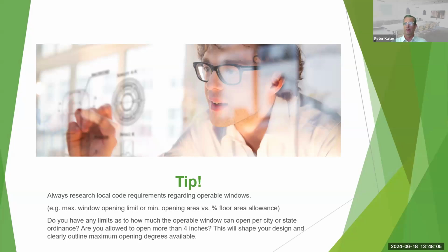In many commercial buildings, when the facade is multi-level, multi-story, the opening of the upper levels is typically limited in many cities to about 4 inches maximum. This is to stop objects falling out, or people falling out of the windows. It's a safety requirement that typically doesn't apply on the ground level, but this also needs to be considered in the natural ventilation system design.